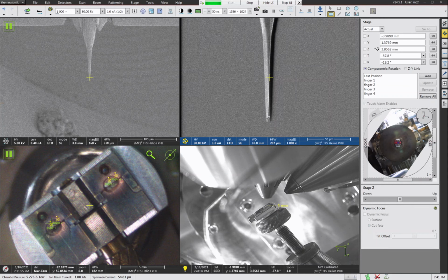If I double click on the end of the post right now, I'm going to cause the microscope to slam my sample holder into the FIB column, because the software interprets a double click down here as trying to move in the Y direction, but it does a tilt correction on it. So it basically tries to move it in, it's like a divide by zero error. So it tries to move it an infinite amount of distance towards the column. So don't double click on the FIB image when you're at the minus 38 or 37 degree tilt. You're likely going to screw everything up.